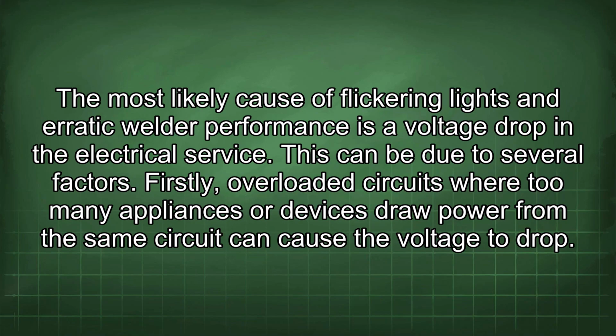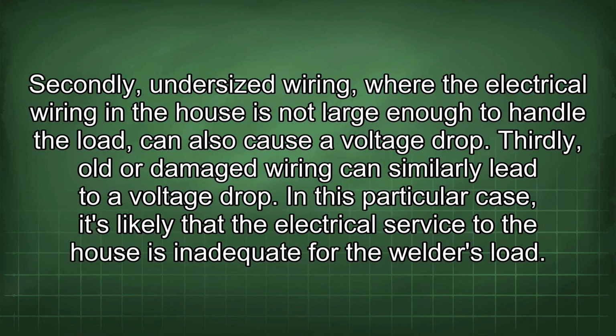The most likely cause of flickering lights and erratic welder performance is a voltage drop in the electrical service. This can be due to several factors. Firstly, overloaded circuits, where too many appliances or devices draw power from the same circuit, can cause the voltage to drop. Secondly, undersized wiring, where the electrical wiring in the house is not large enough to handle the load, can also cause a voltage drop. Thirdly, old or damaged wiring can similarly lead to a voltage drop.